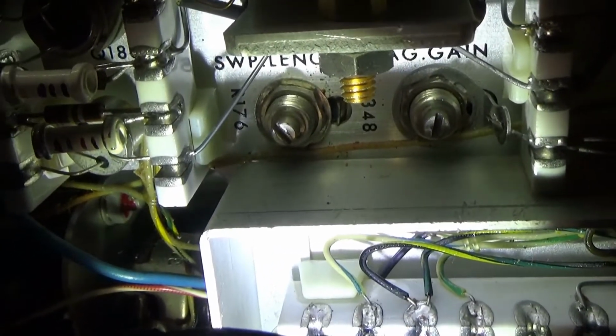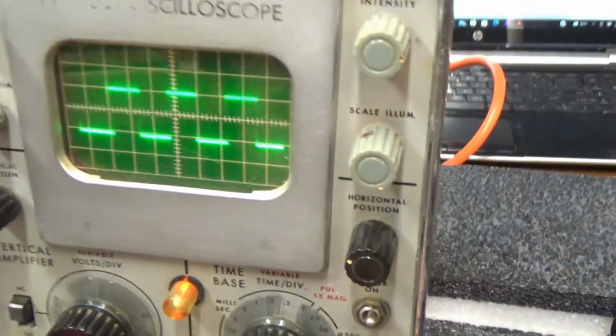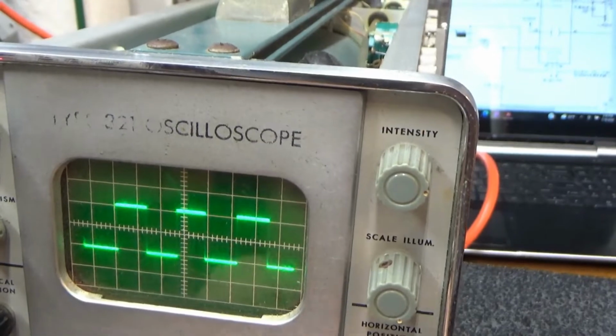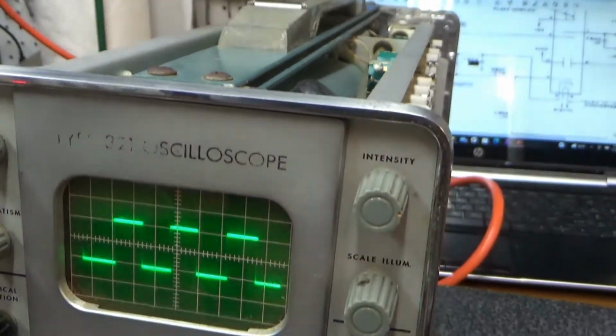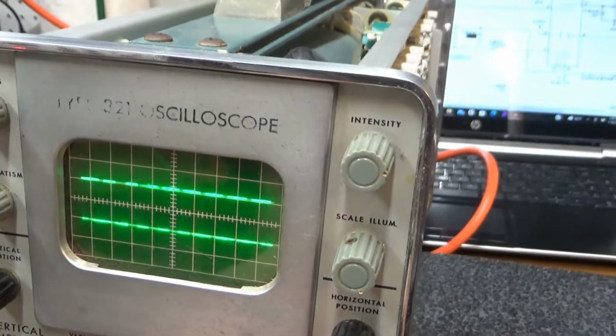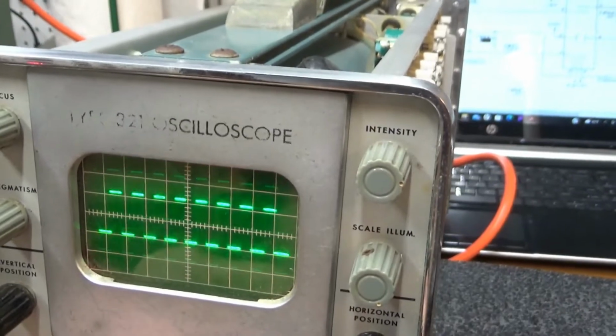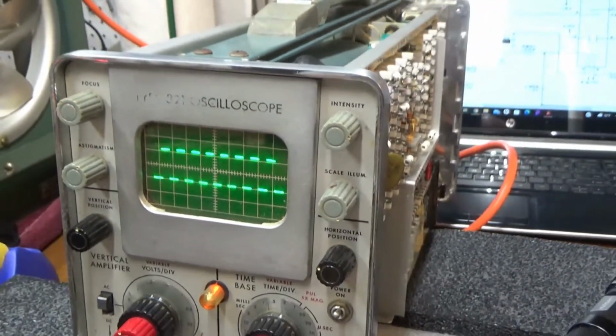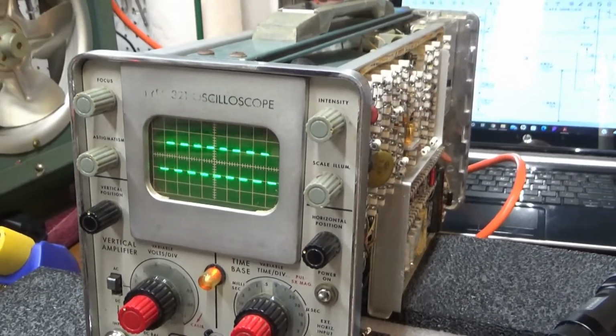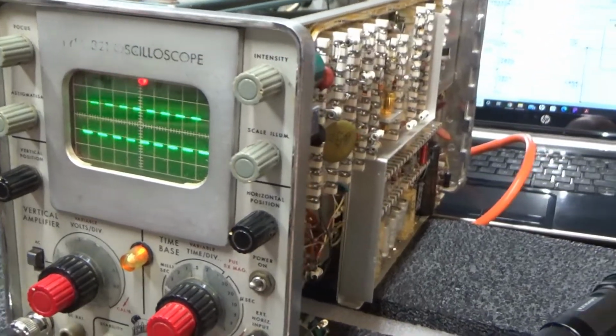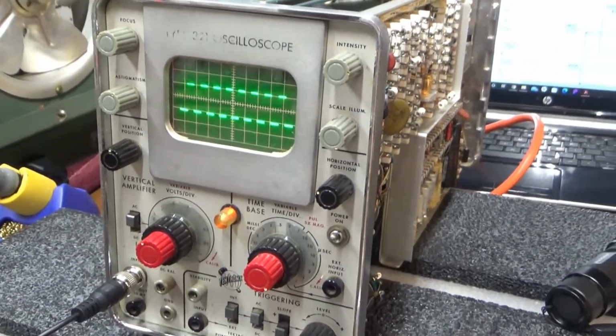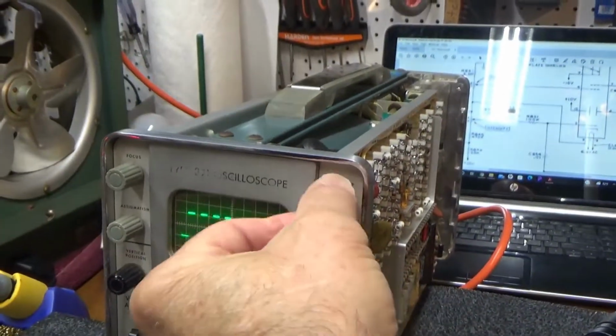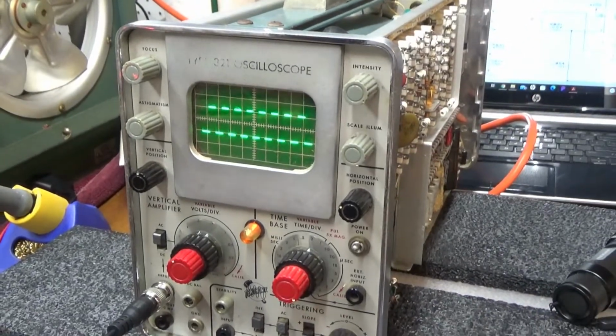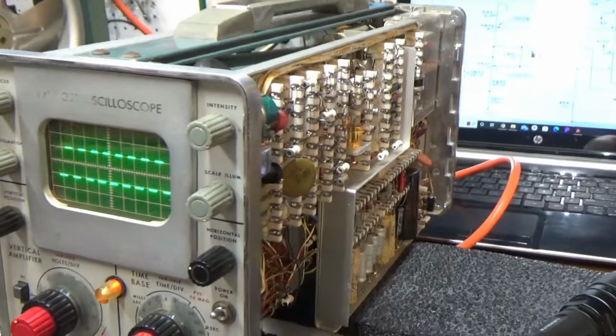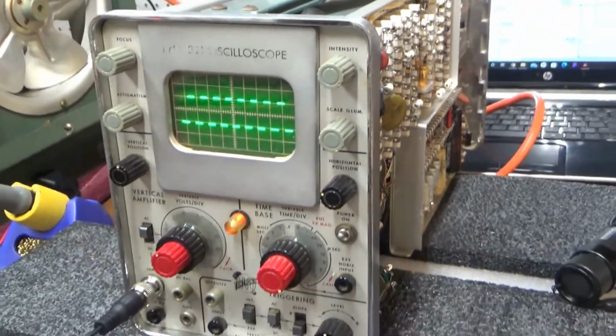I found an adjustment called sweep length right here on the side of the scope, and I tweaked that a little bit and got the display to go all the way across the screen. That's looking much better. I'm still playing with the intensity to try to clean that up, but it looks like it's working. So I may just call this one fixed and put the sides back on it. It probably needs to be calibrated, but I'm not really going to use this as a real scope. I just wanted to get it working. Maybe I'll go through and do a calibration just for fun, but looks like it's there. Well, let me leave the sides off because maybe I'll tweak a little bit. But I think I'm going to call this a wrap on the video.